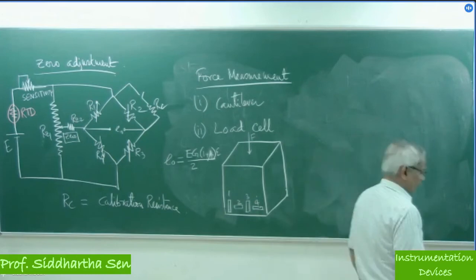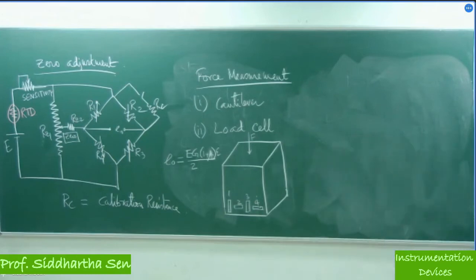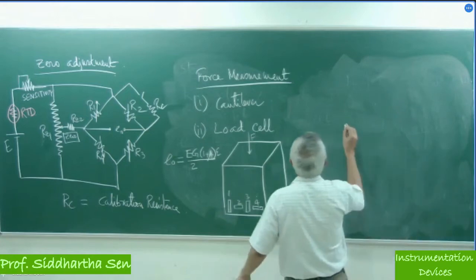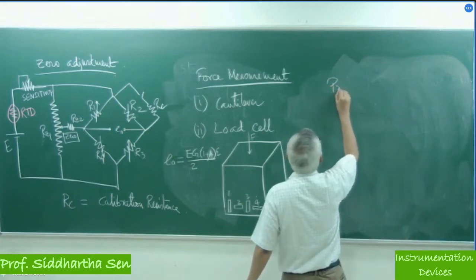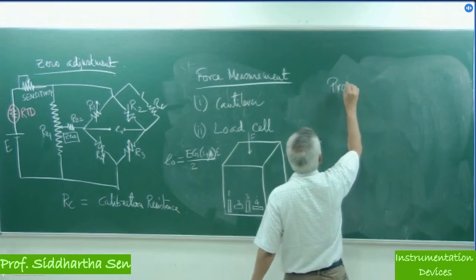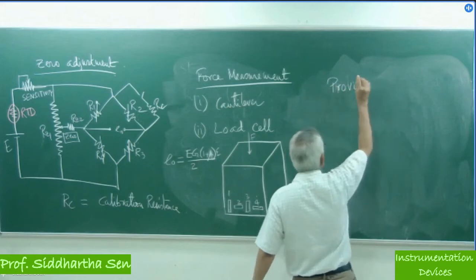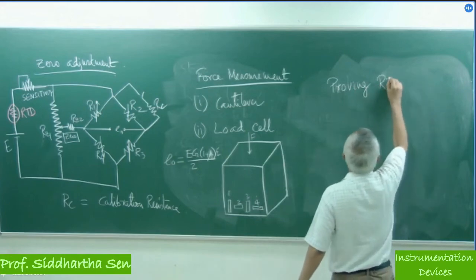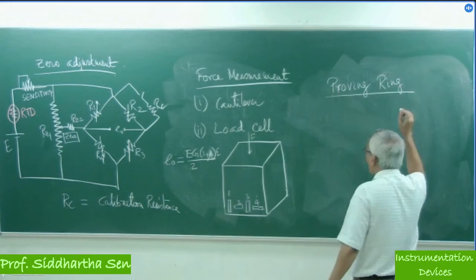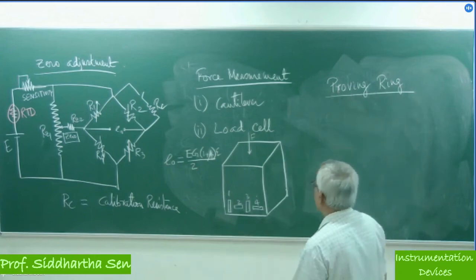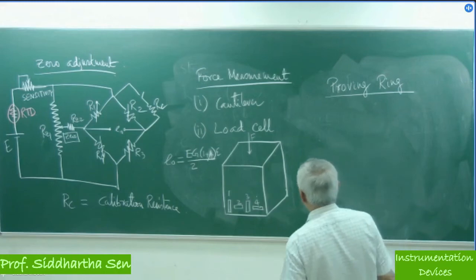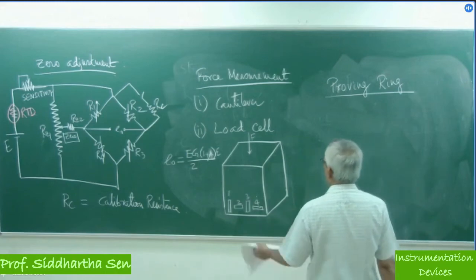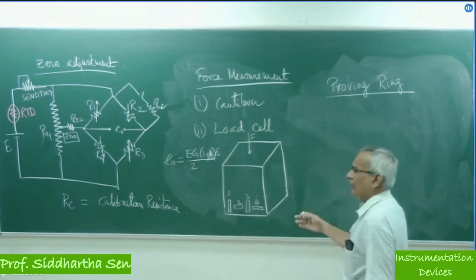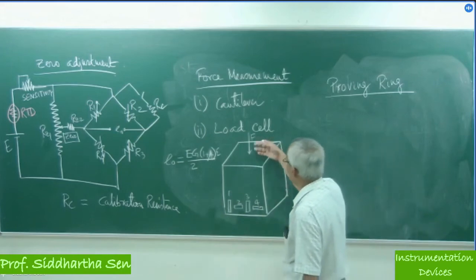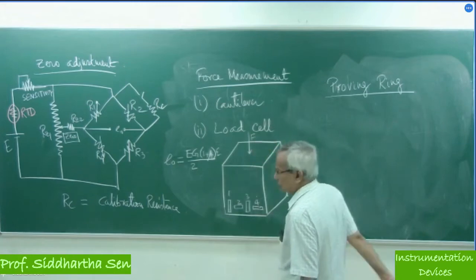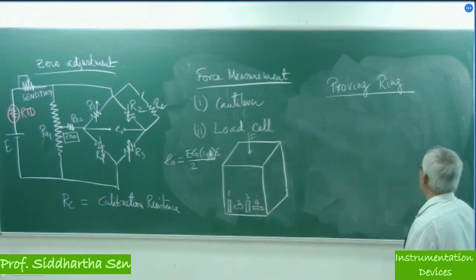The third application is interesting — for measurement of force — because strain gauges have several applications in mechanical engineering. One of them is the proving ring for force measurement, since we often need force measurement in different orientations and areas. For example, if we want to measure tensile force, a load cell can give compressive force, but it cannot measure tensile force.